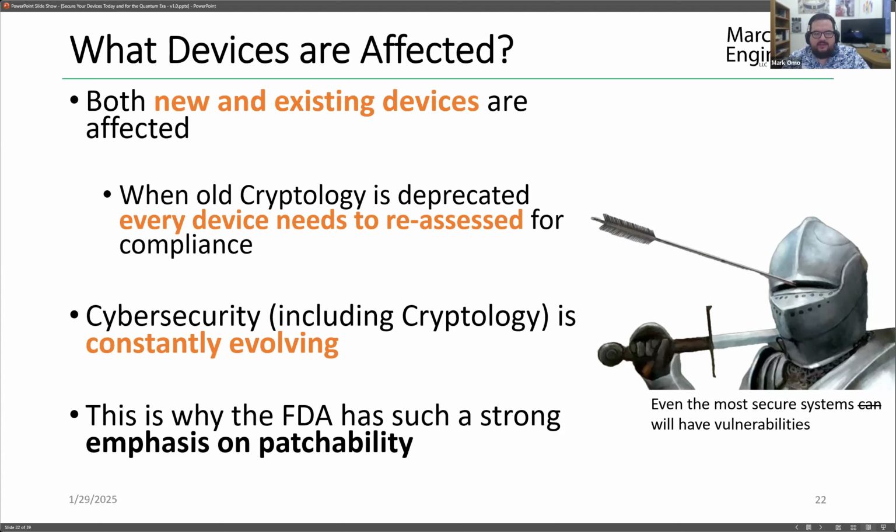And really, cybersecurity, including cryptography, is constantly evolving. It's not like we can have nice testing that shows we achieved something and now it's done. Our device isn't going to magically no longer diagnose properly or something like that, or magically stop being biocompatible. But that is the case for cybersecurity. It's this shifting target that you have to constantly look at throughout the life cycle of your device, like Axel talks about. And this is one of the reasons why patchability is really one of the most important topics, because we expect things to change.